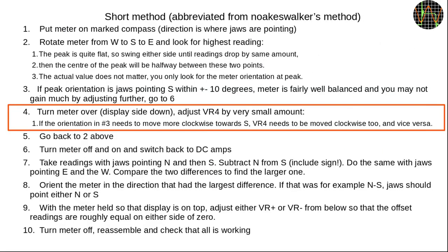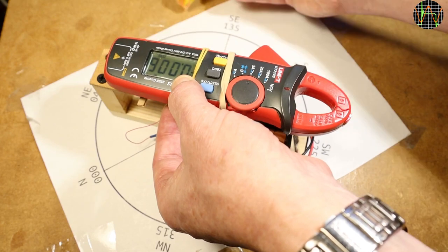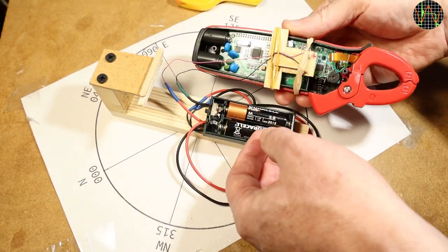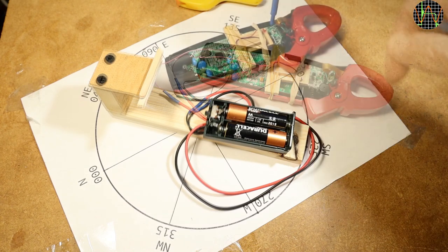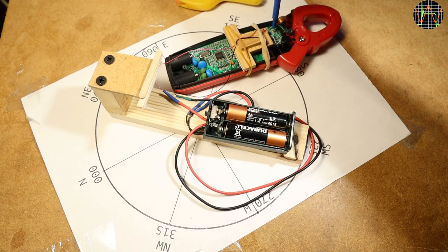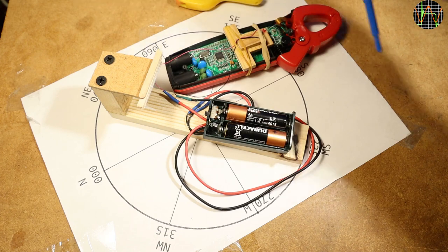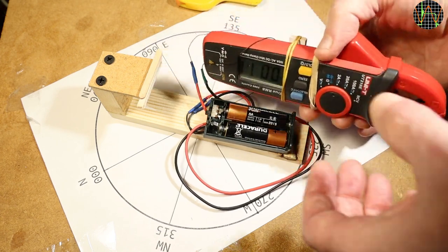Adjusting VR4 is covered in step 4 of the short procedure. It assumes that the meter is upside down and you are looking at VR4 when doing it. This is how you would do it. Take the meter off the stand, turn it around and give VR4 a tiny nudge. Since my meter is now aligned after many hours of work, I am too scared to even touch it. After the VR4 adjustment, you start a new sweep. You will get completely different offset values so no point in remembering any values of the previous run.